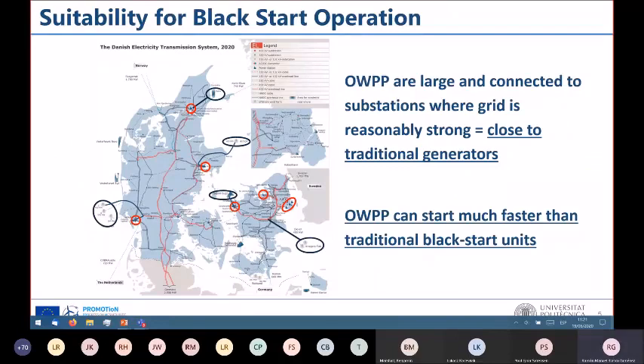Why are offshore wind farms particularly suitable? In the restoration process, the first thing the restoring unit has to do is power up the ancillary services of the traditional units. This is the case of Denmark, but it's the same in many other countries: the wind farms are closely connected to traditional units just because the grid is stronger there. So they are particularly suitable for this kind of situation. So what would we like to do? We would like to achieve a green black start from wind power plants. This is a big challenge, but if we can allow wind power plants to be plugged in earlier in the restoration process, that's also a big contribution to mitigating the effects of a big blackout.